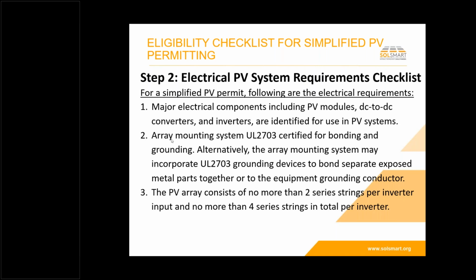Array mounting systems, UL 2703 certified for bonding and grounding. So there's a new UL standard. Well, it's not that new, it's probably 4 or 5 years old, where products now are listed to this standard for bonding and grounding the aluminum frames, the racking materials, all that kind of stuff. And alternatively, they could use grounding devices to bond things together. Those are the two different ways that we ground and bond stuff, and that's certainly a big concern of local jurisdictions, that things are well grounded and well bonded together.